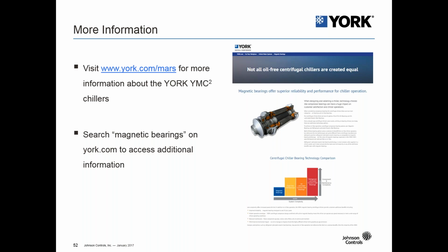Great. We had another question that asked, how is it possible to operate in an inverted manner while still circulating the refrigerant? Yeah, that's a question that we do get fairly often when we are talking about inverted and minimum entering condenser water temperatures. Typically, the customer needs to know what those temperatures are in terms of the water circuit. So the entering condenser water temperature and the leaving chilled water temperature usually have to have some type of differential at various chiller loads.